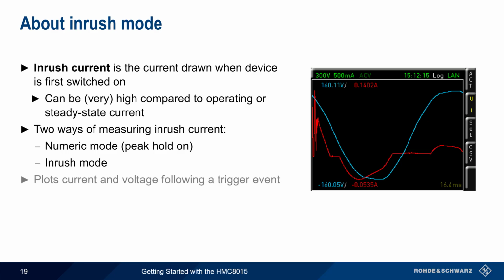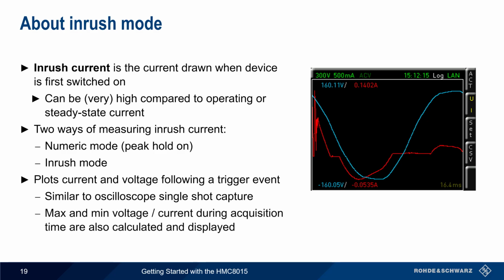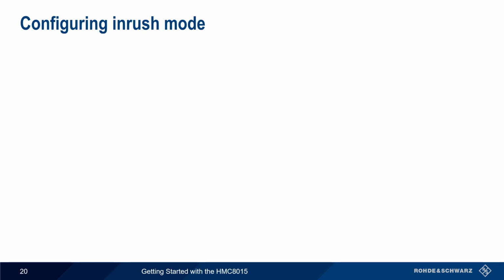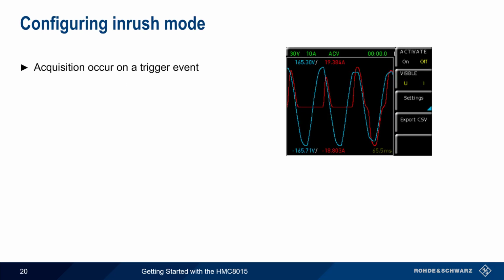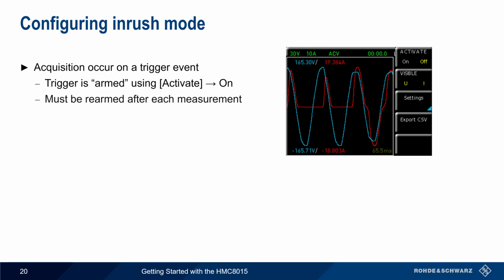In inrush mode, the voltage and/or current are plotted following a trigger event. This is similar to making a single-shot capture on an oscilloscope. In addition to plotting these values, Inrush mode also numerically displays maximum values of voltage and current during the acquisition time. Inrush mode measurements do not run until a trigger event occurs, and this trigger must first be armed using Activate On. The trigger must then be rearmed after each measurement.